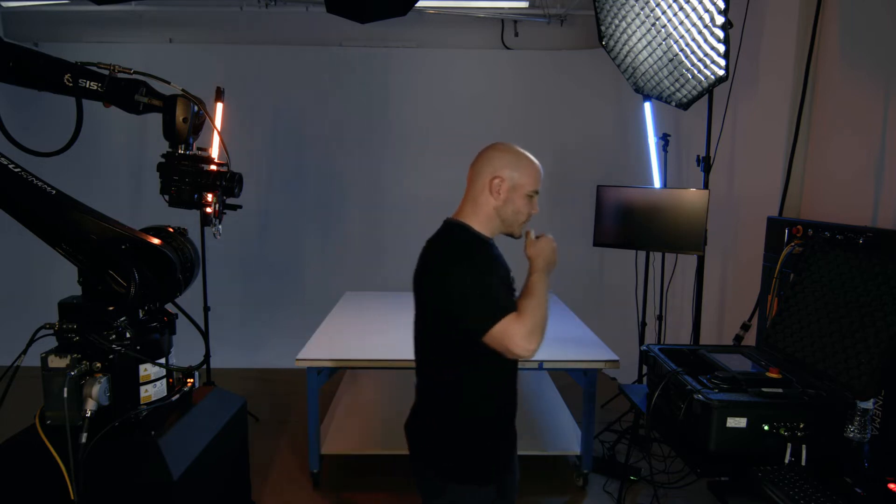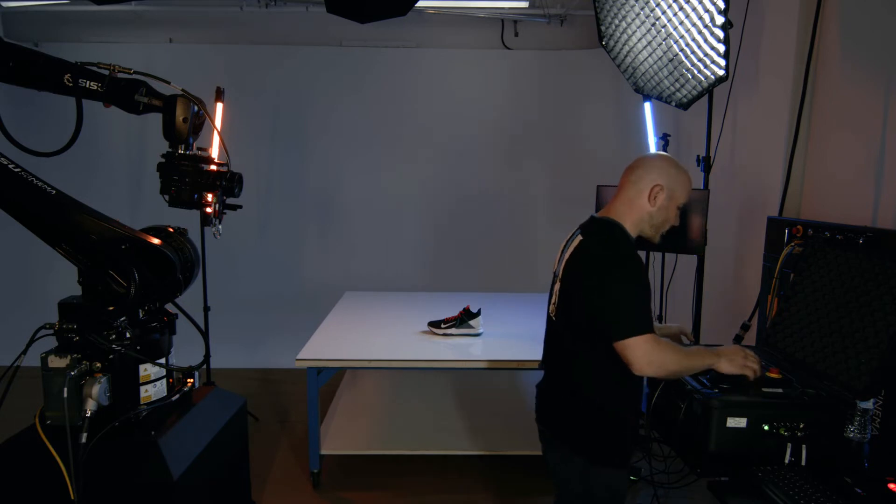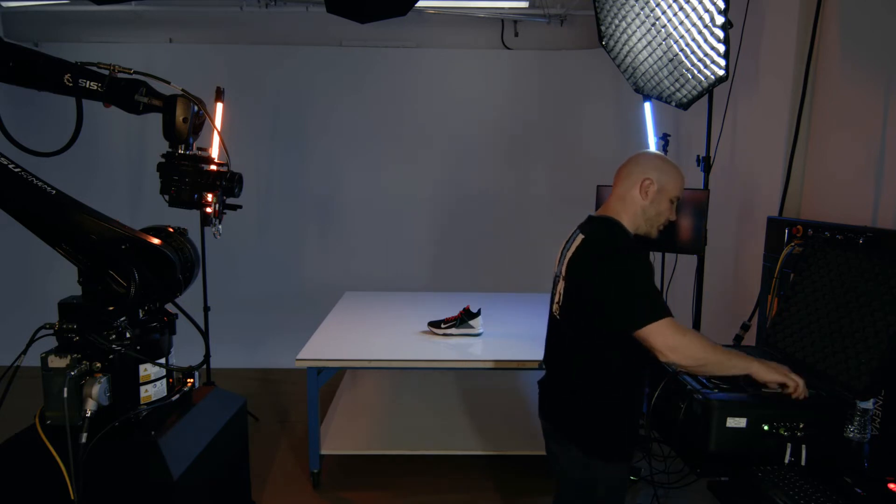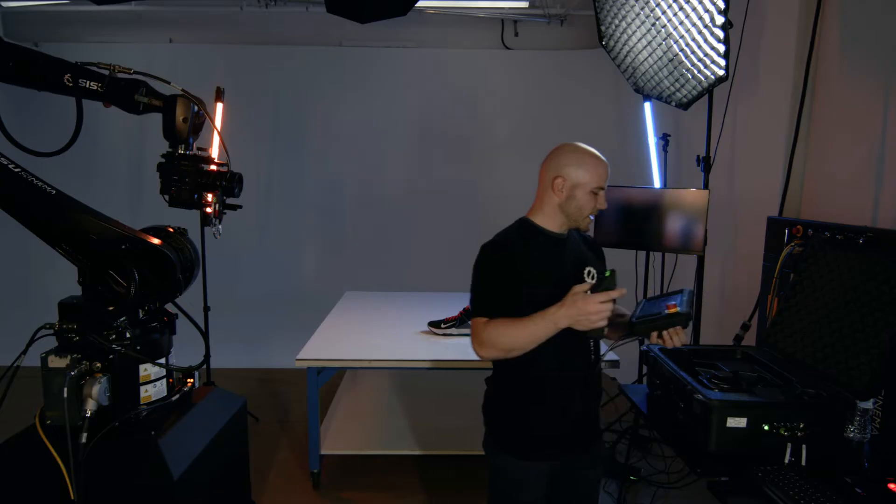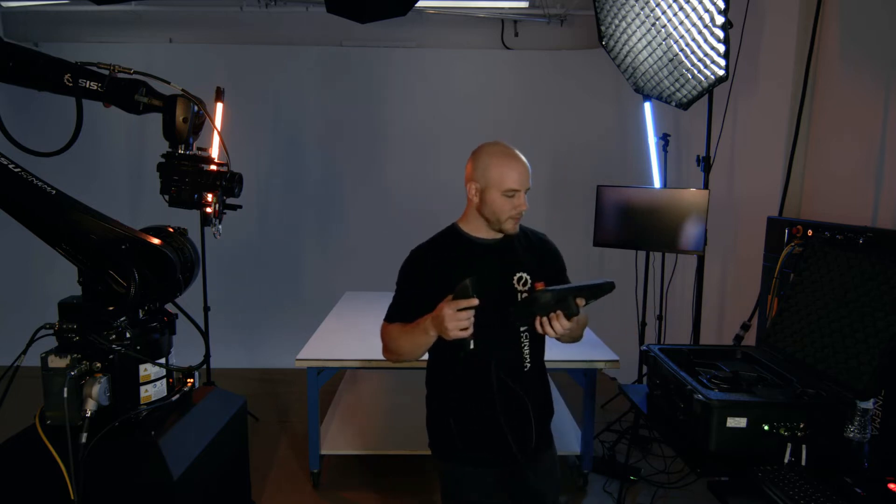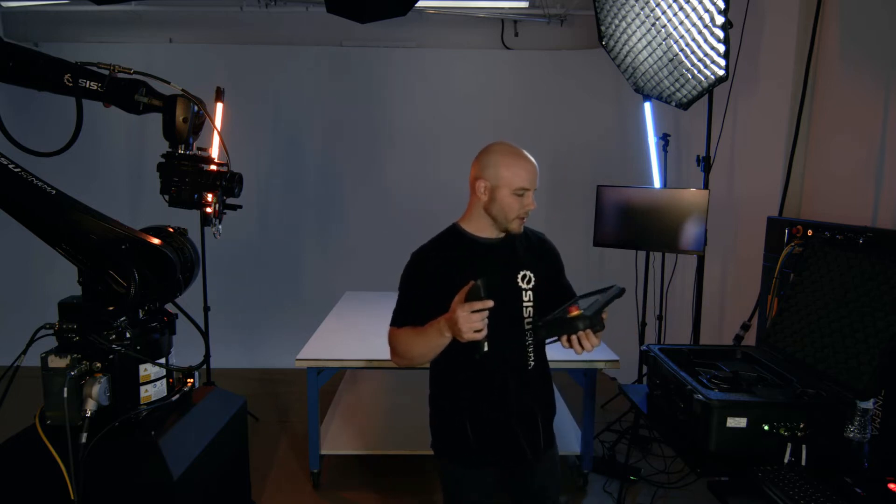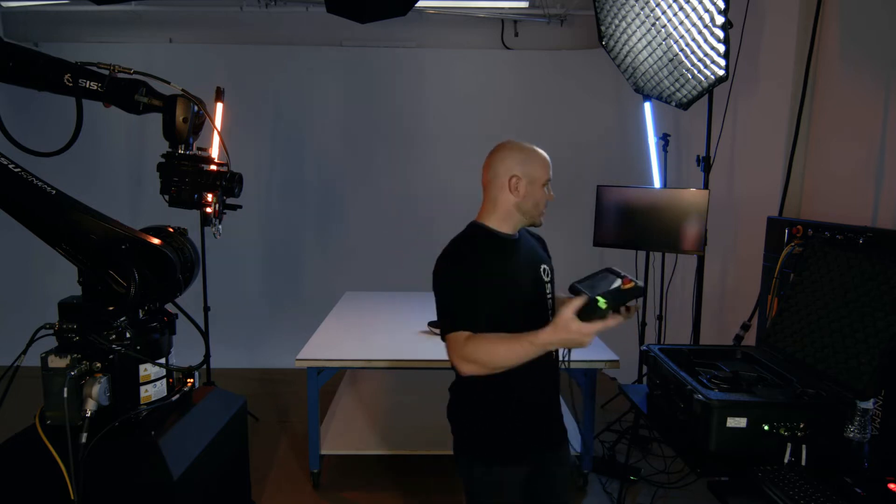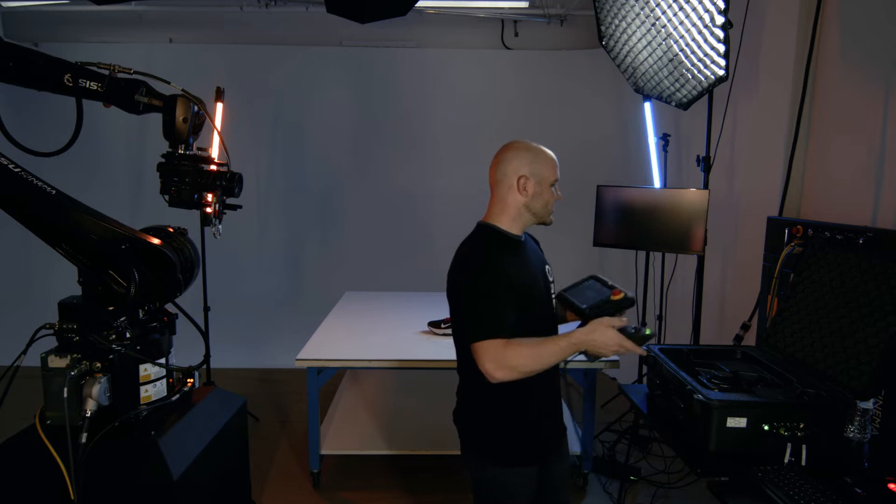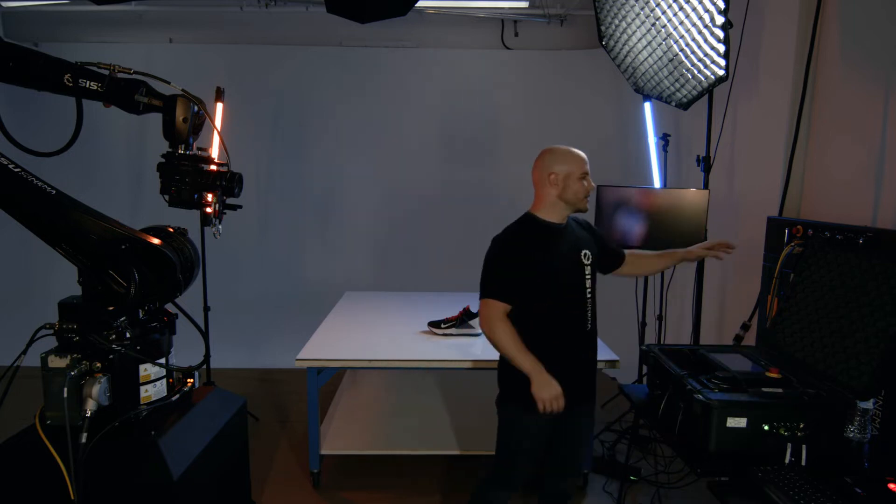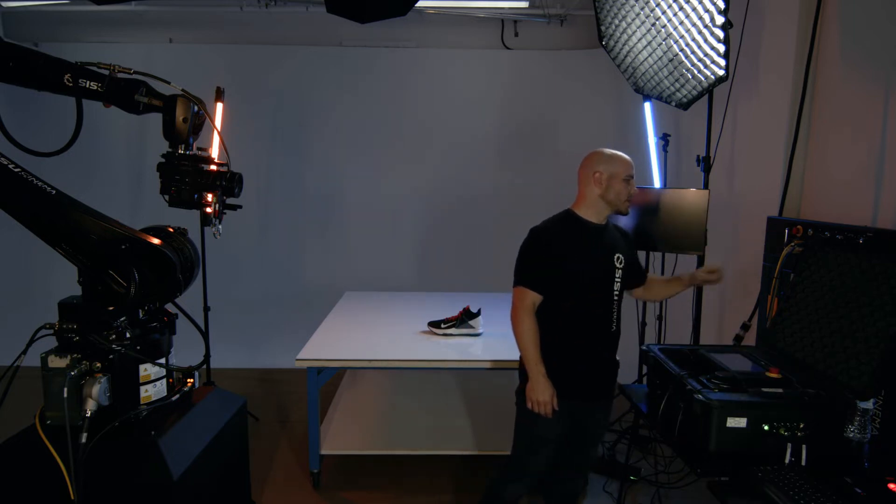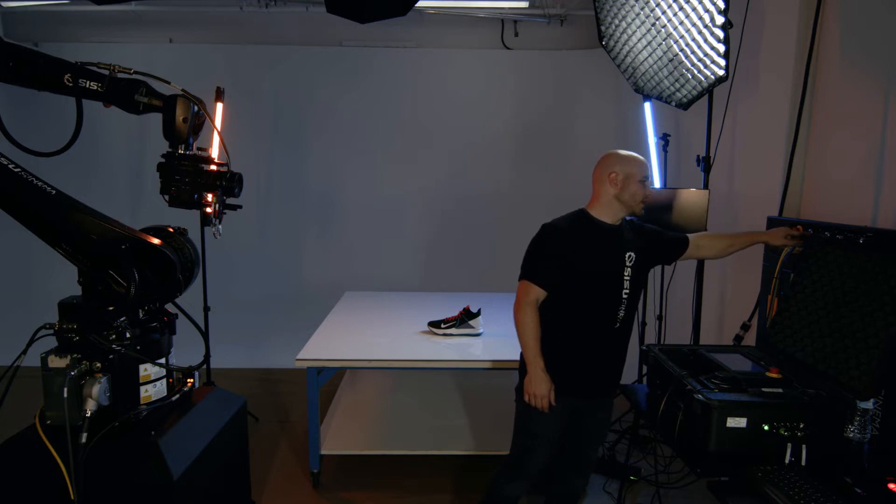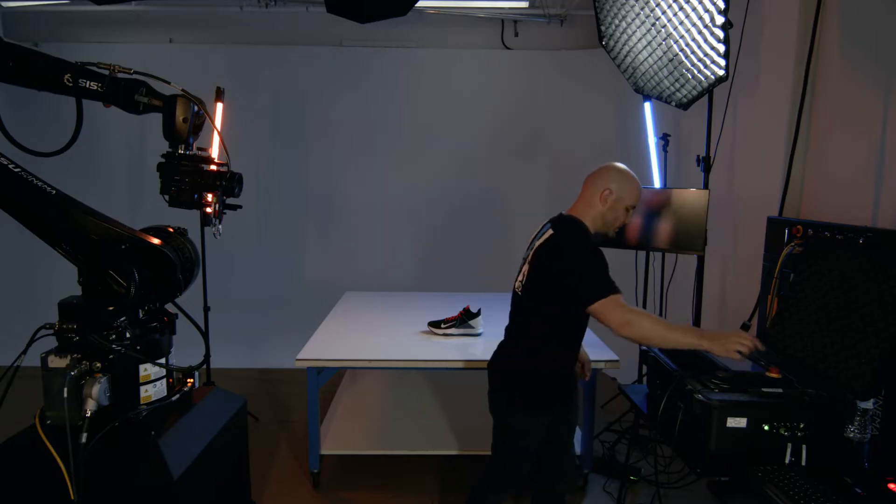So let's go right over here into Sisu Lab. Looking at the timeline, I'm holding the enable button, trying to move it, never clicks in, you know something's wrong. If I look at the sim, that safety reset button is flashing and it will not reset. All my e-stops are out. I know it's not an e-stop issue either.